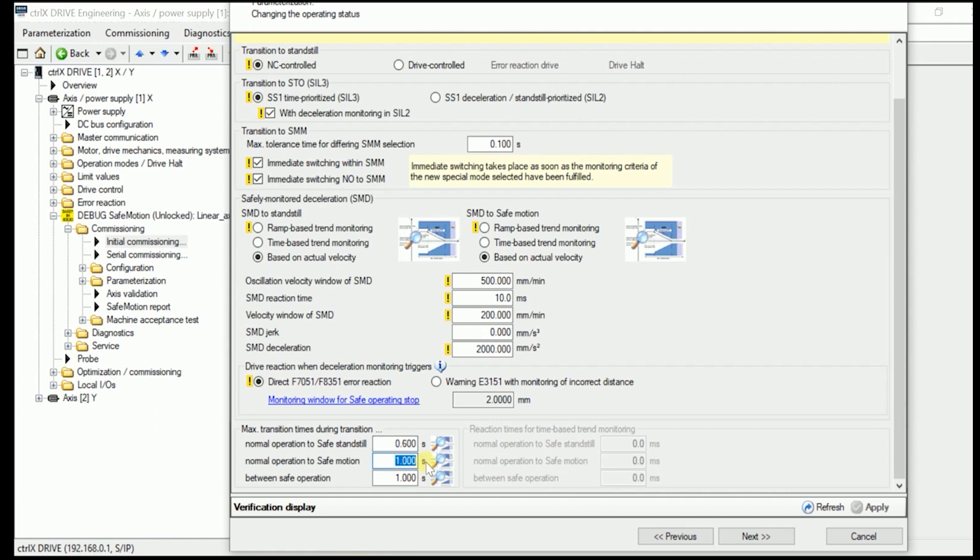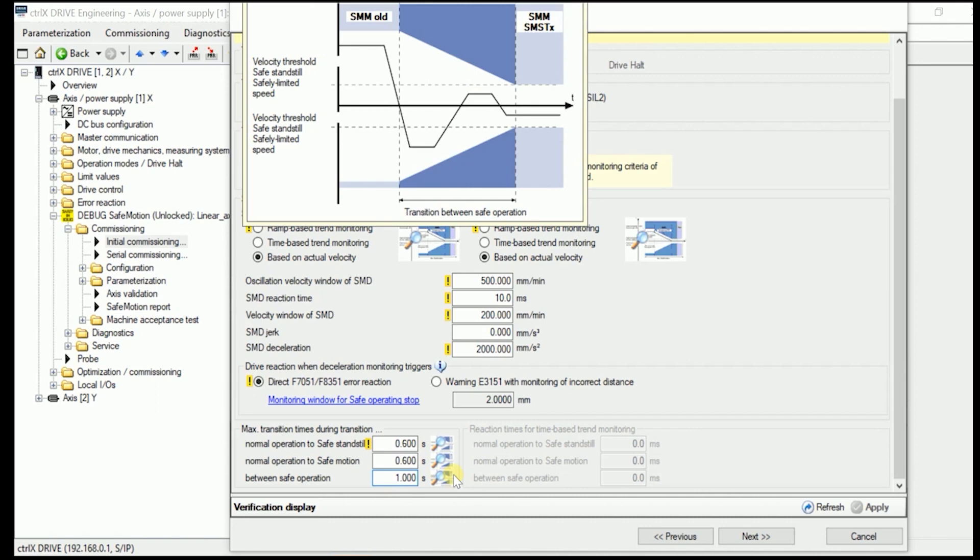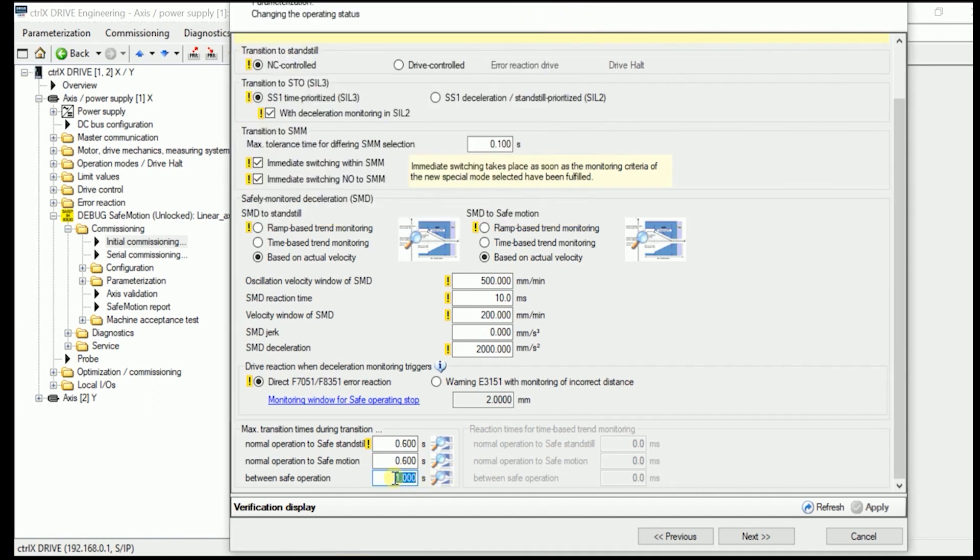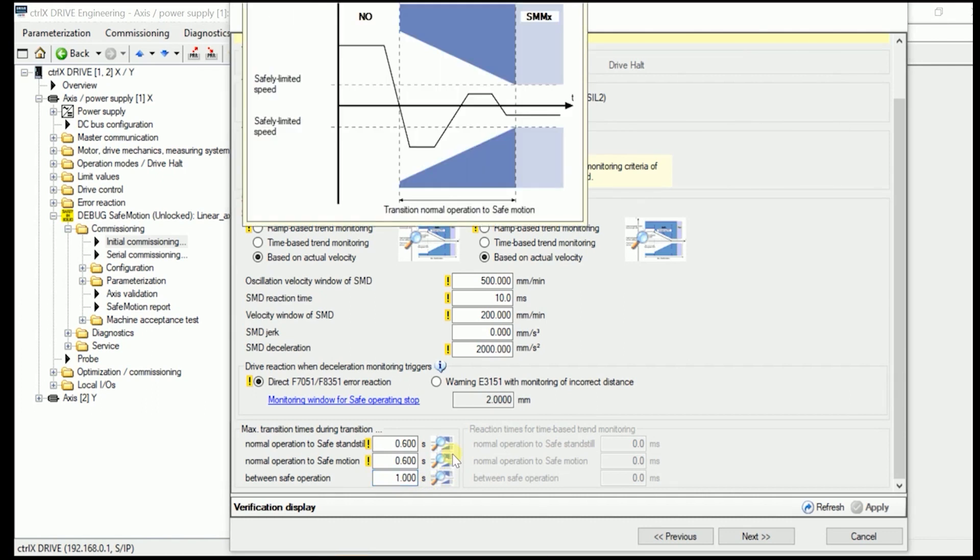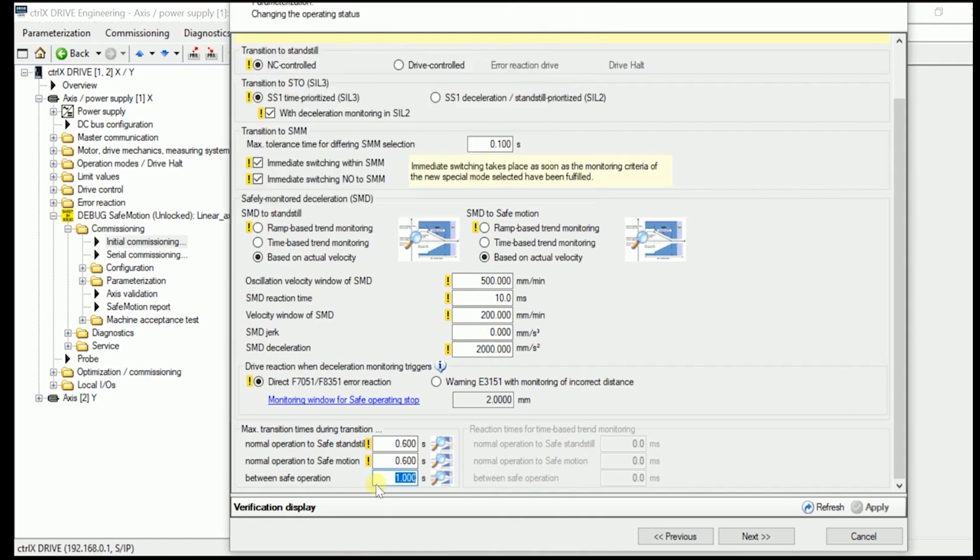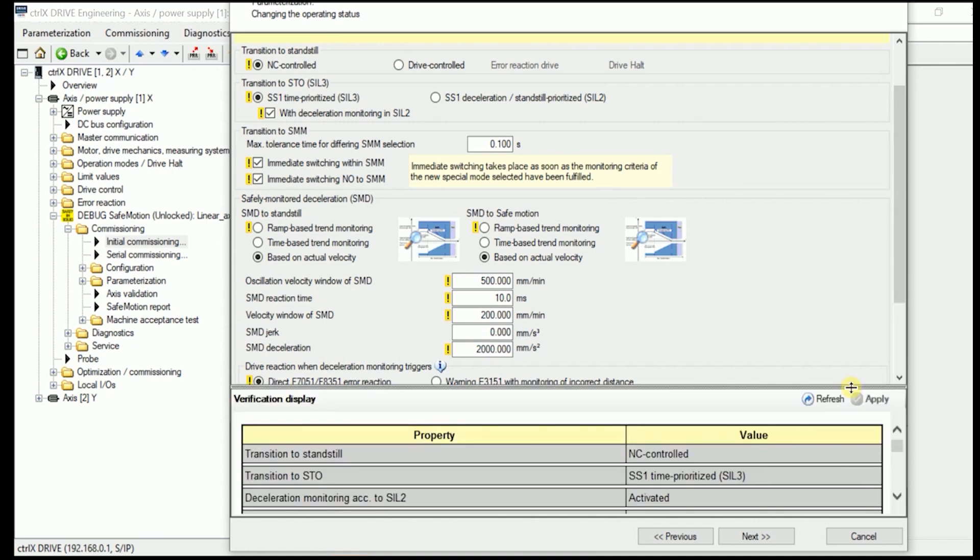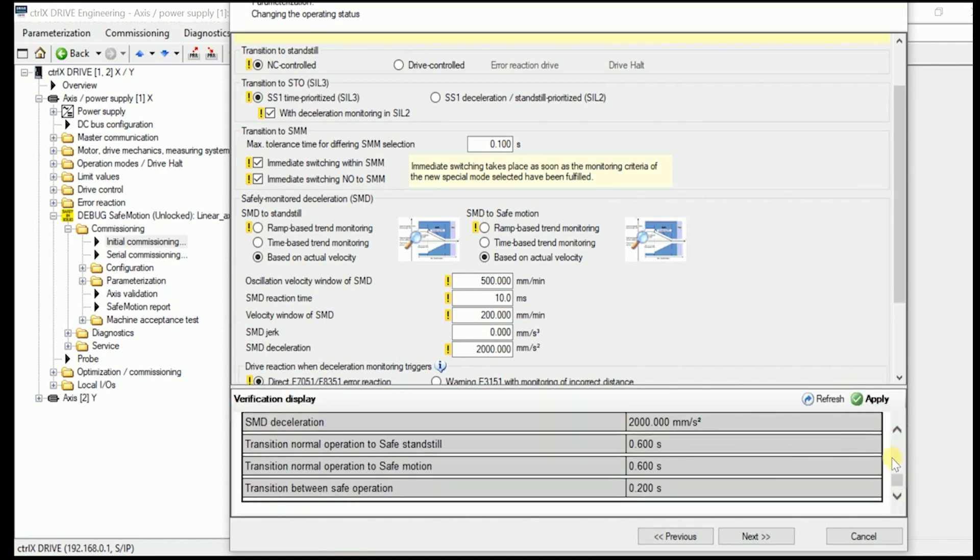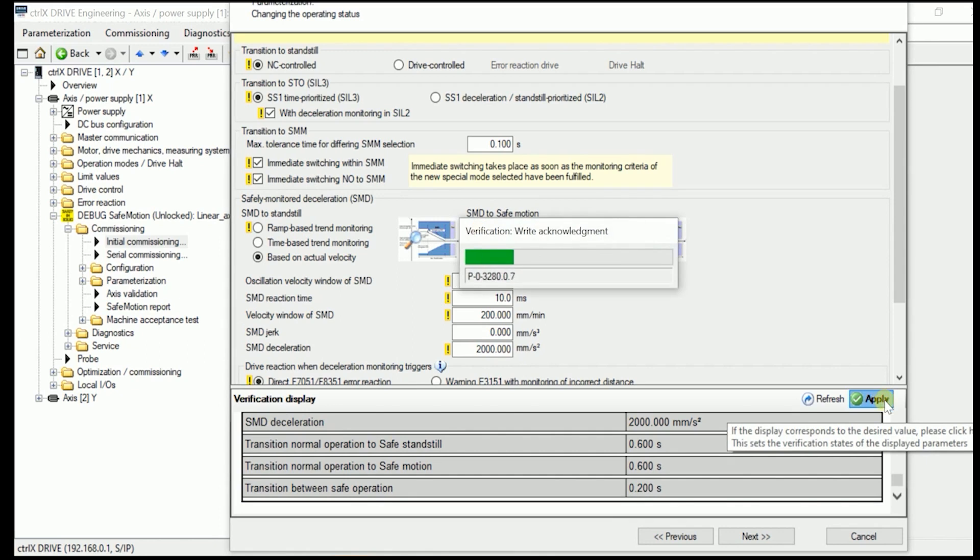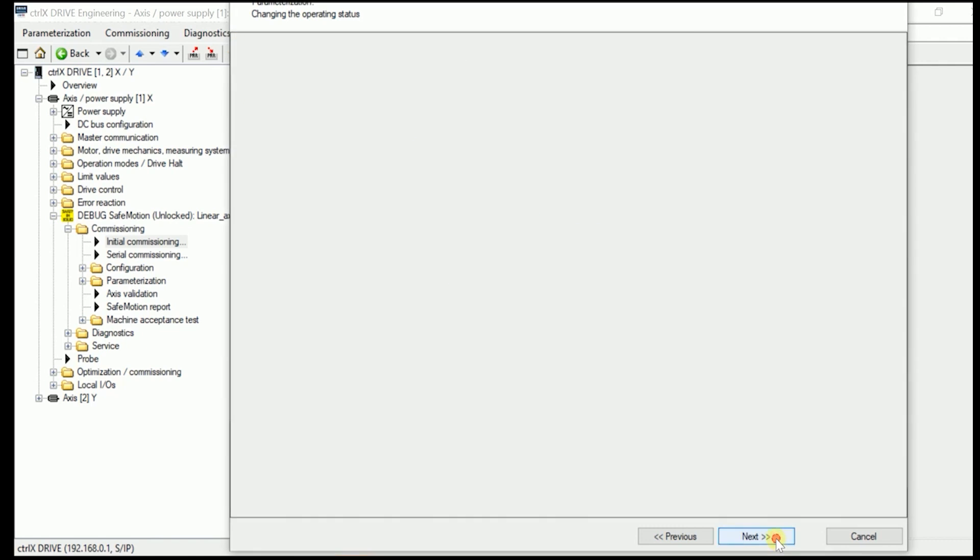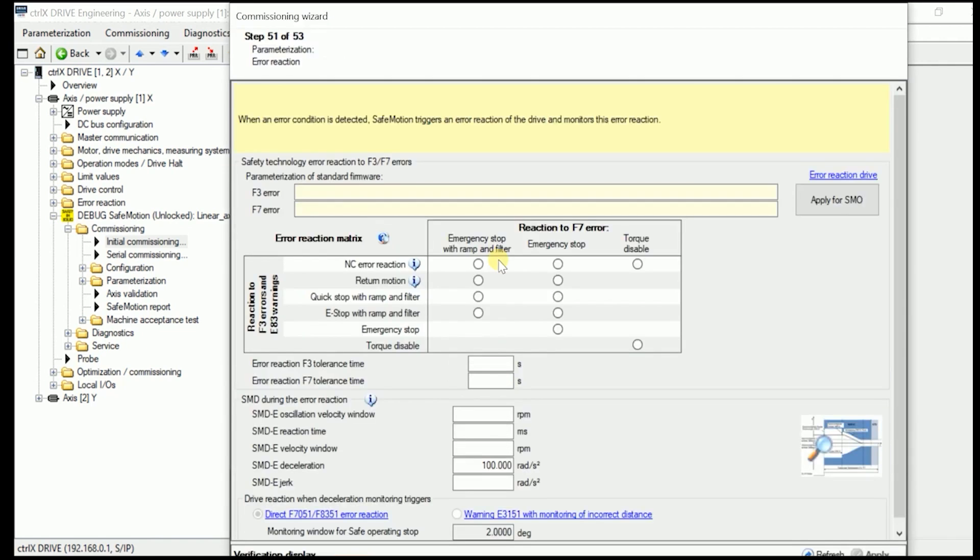We are not implementing here SMD jerk. But we are having here the deceleration where this safe motion monitoring goes on. Usually we recommend in here about 60 percent of the value normally active for the normal operation. As well in here if we take here into account the 2 meter per second from 15 meter per second squared. Then that takes around 0.5 seconds. So now we put in here a little bit more in here. Similarly in here same for the normal operation to safe motion. And if we would have several different safe operation modes or safe motion modes, then of course to come from the one to the other then it would be a little bit less like 0.2 seconds.